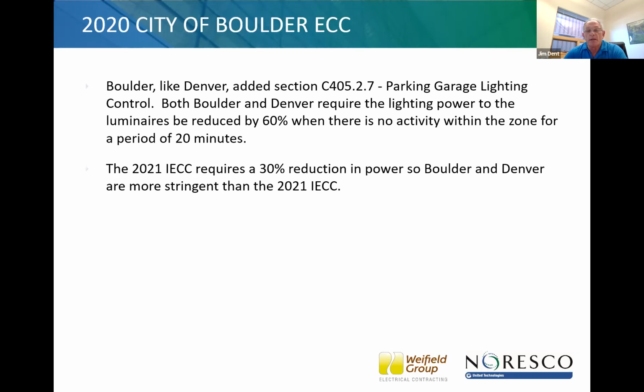Boulder, like Denver, added section C405.2.7, parking garage lighting. They both require lighting power to be reduced by 60%, and they're both more stringent than the IECC. So I think the amendments will change, because many of the requirements in the 2021 IECC reflect what's in the Denver and Boulder requirements, but Denver and Boulder will probably keep the 60% requirement in their amendments, okay?